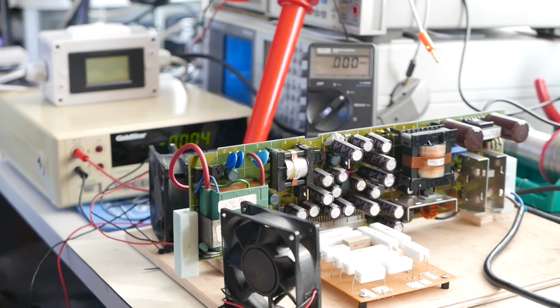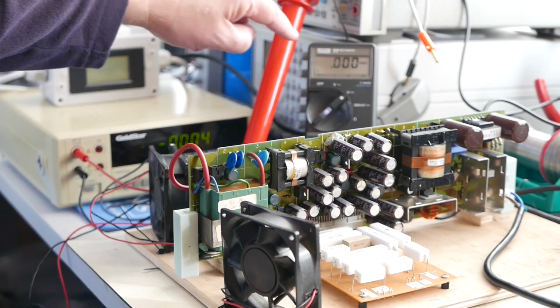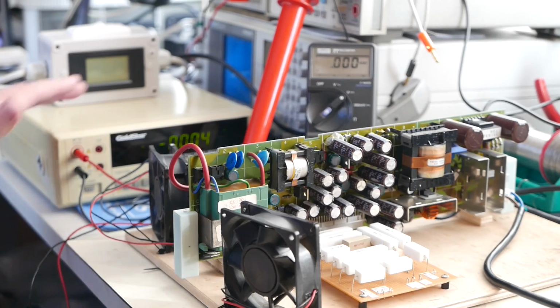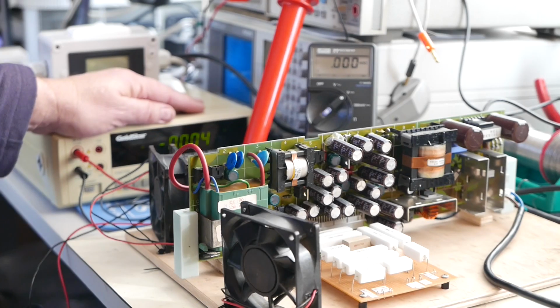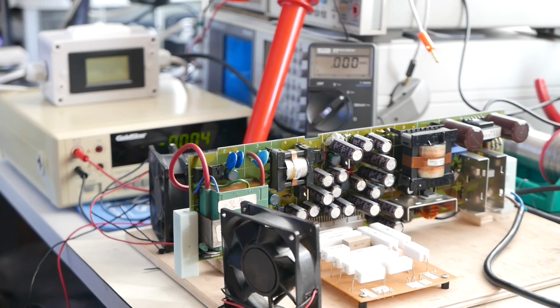I've got my probe set up on the high voltage output on this meter, so that should stay at 0. I've also got the gold star meter set up to monitor the -12 supply, because the voltage supply protection monitors the -12 volt supply, on the basis that if any of the supplies is overloaded, that will be seen on the -12 volt supply. If one goes down, they all go down. My expectation is that the power supply will instantly cut out and the power consumed will drop to about 16 watts, which is what it was before. I shouldn't see a voltage from the high voltage multiplier because that is disabled and has no power supply.